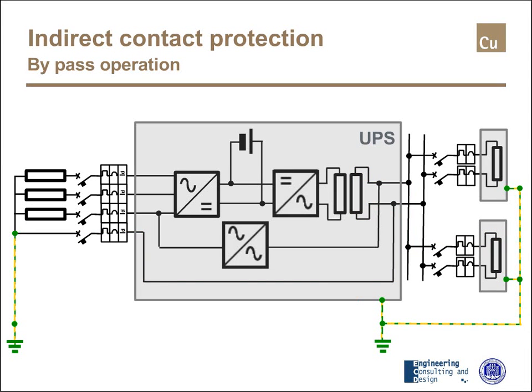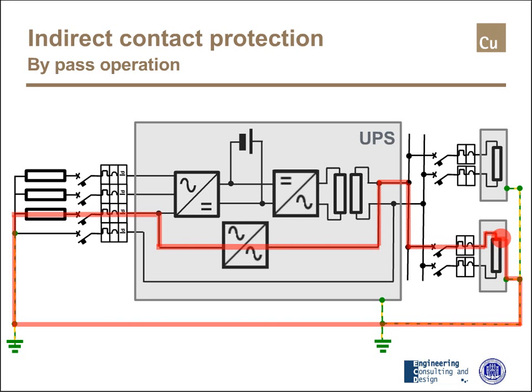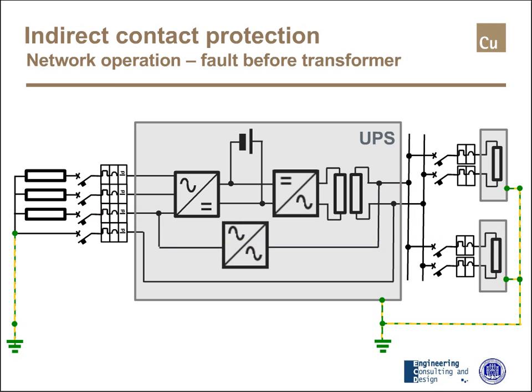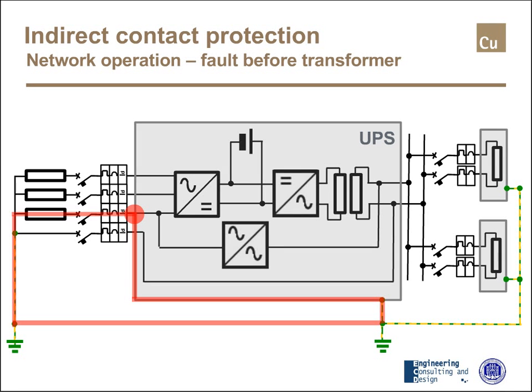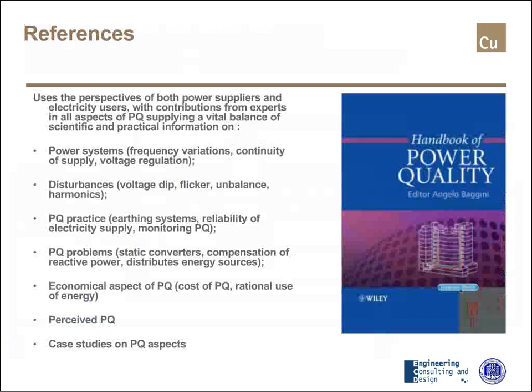If the load is fed by the bypass, the current is slightly different, but again this fault current allows the trip of the RCD protection, so the system is still protected. The same applies if the fault is before the transformer — the fault current is different but still sufficient to trigger the trip of the protection. That's all.